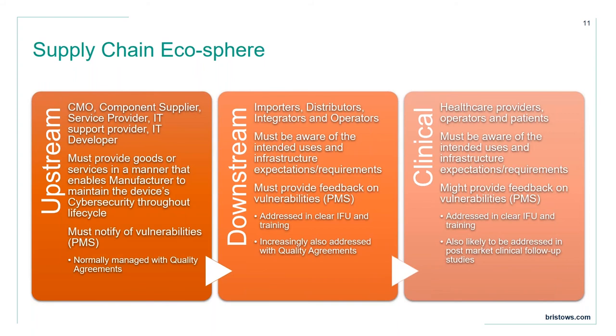In terms of how to go about flowing both the minimum IT requirements and the new PMS obligations through the supply chain, it seems to us that a slightly different approach is required for each. For the minimum IT requirements, a logical approach would be to create a master description or specification that acts as a single source of truth and point of reference, which can then be reproduced whenever needed, for example in the IFU and in contracts with operators and other stakeholders.